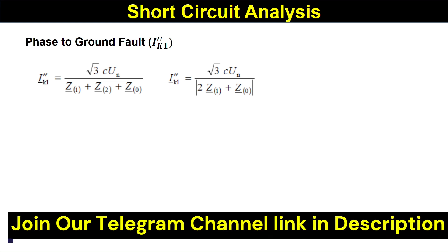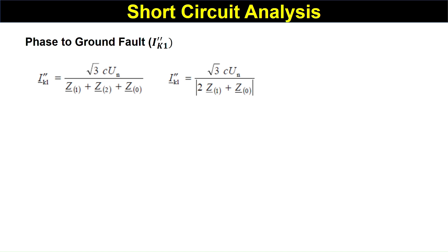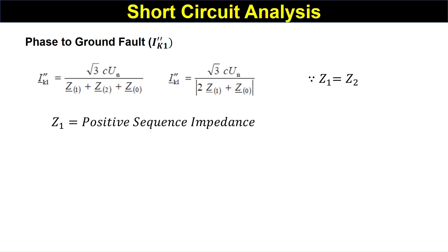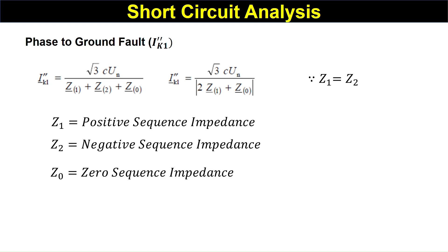First we will calculate the phase-to-ground fault, represented by I_k1 double dash. I_k1 double dash is equal to root three times c_un divided by Z1 plus Z2 plus Z0. Here Z1 equals Z2, so it becomes: I_k1 double dash equals root three times c_un divided by twice Z1 plus Z0, where Z1 is the positive sequence impedance, Z2 is the negative sequence impedance, and Z0 is the zero sequence impedance.